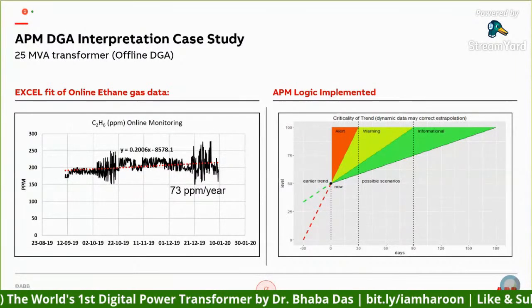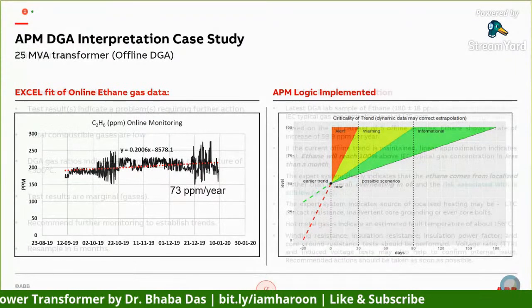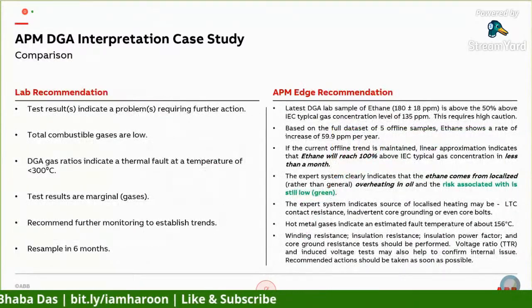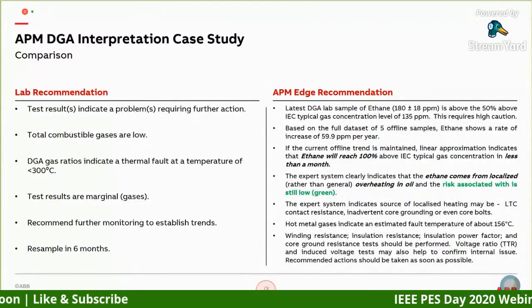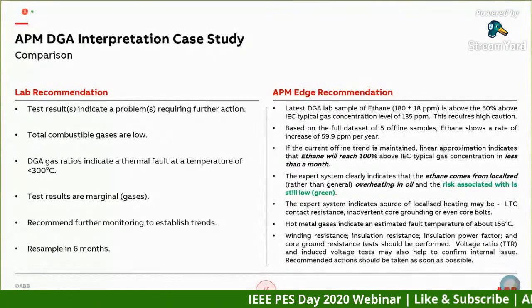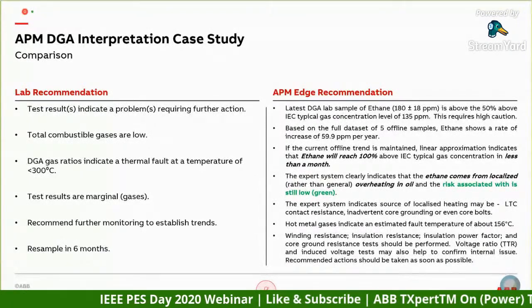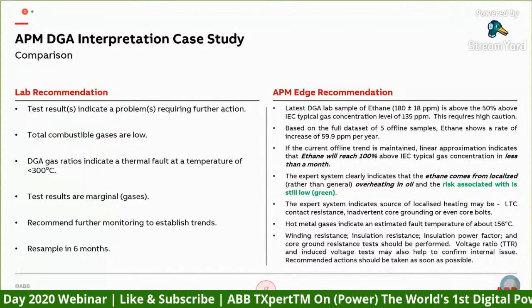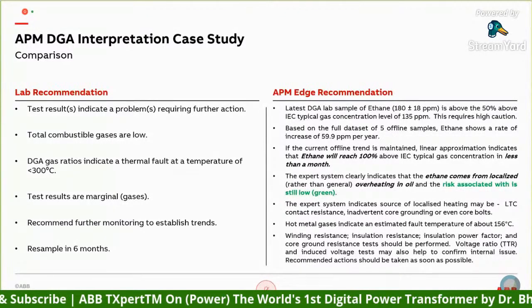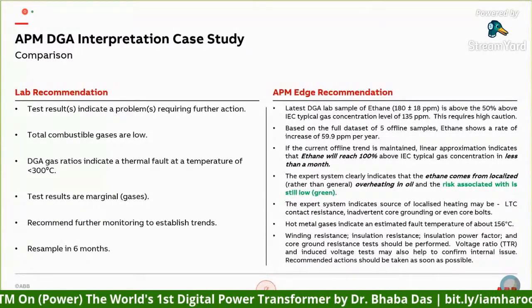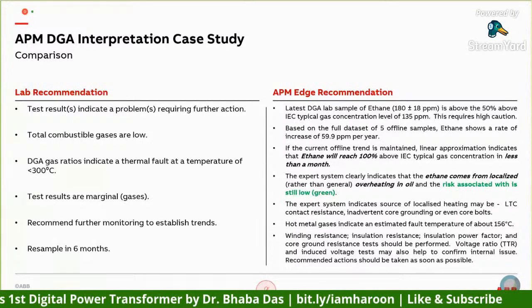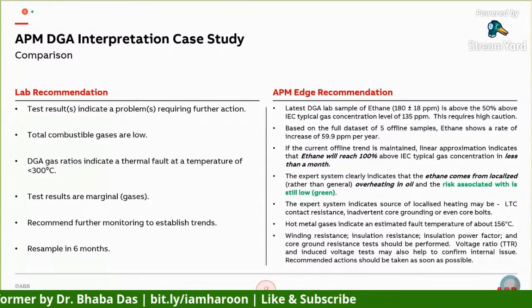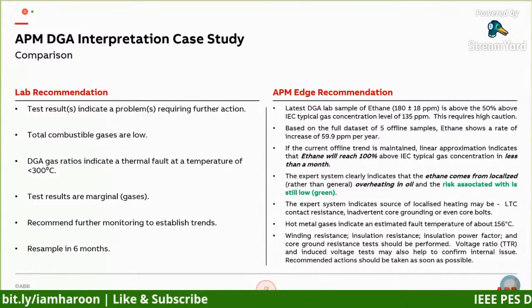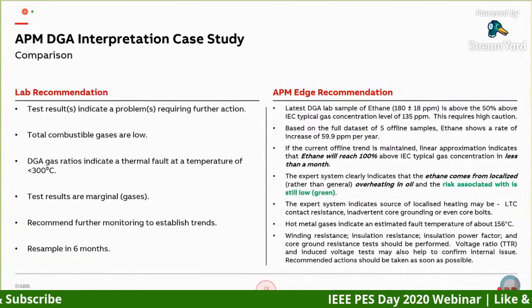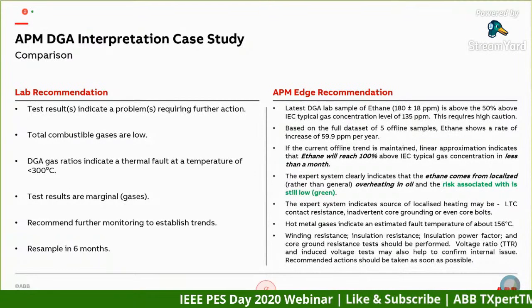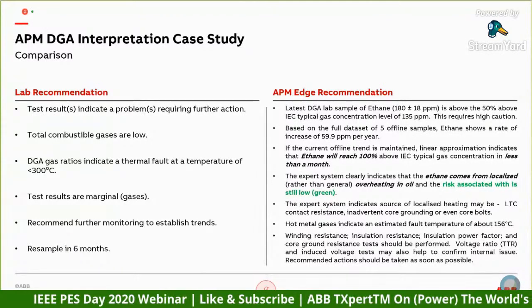This is the power of the software. So if I show you my next slide, you can see the 2 differences. Whereas the lab said, okay, there is trouble, please resample in 6 months' time, we said in 6 months' time, we need to shut down because this is the gas which is going up, risk is low, it is coming from overheating in oil, ethane will reach more than 100% in less than a month. This is the rate of rise.